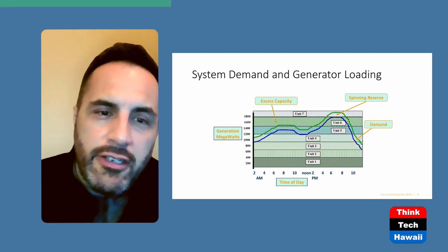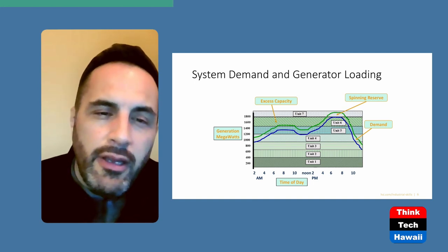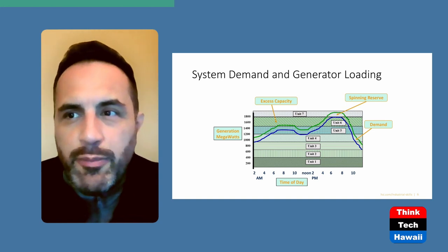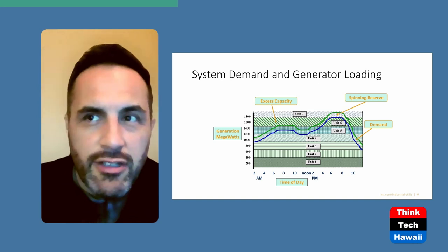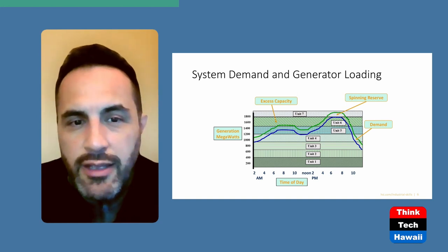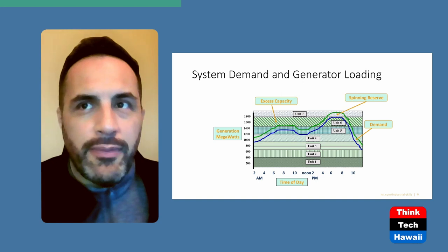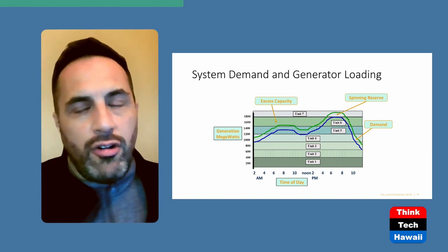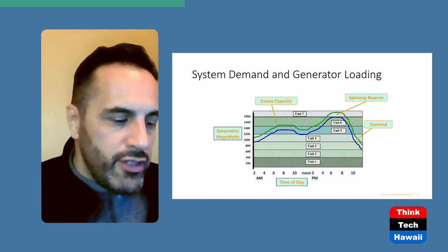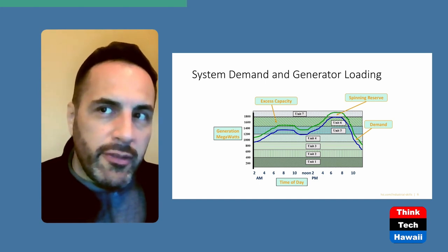Units one and two are inexpensive to run once running, but very expensive to shut down and start up again. The further up you go to units three, four, five, and six, the more expensive they are to run, but they're quicker to start and shut off. Everything has a startup and shutdown cost. Units one and two have very expensive startup/shutdown costs but very inexpensive running costs, which is why they're kept running all the time — these are known as base load units. If you're forced to shut these down because of excess renewable generation, you incur significant costs in maintenance, fuel, and emissions, and you also lose a lot of system inertia.